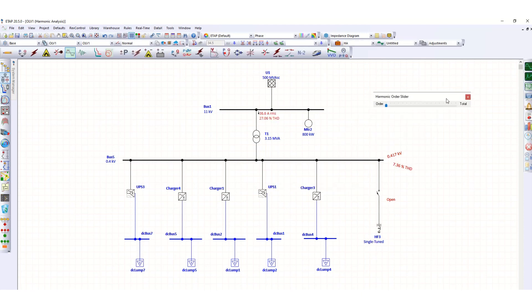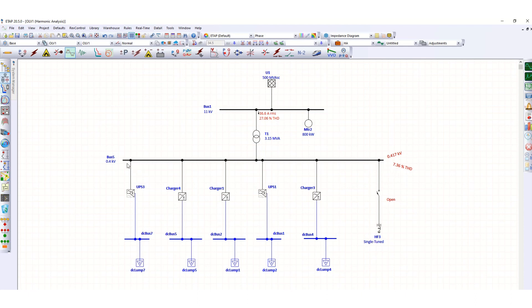Now you can see here THD value is 7.36 percent in bus 5, and here upstream you can see 27.06 percent THD. So here almost 27 percent and here 7.36 percent THD.